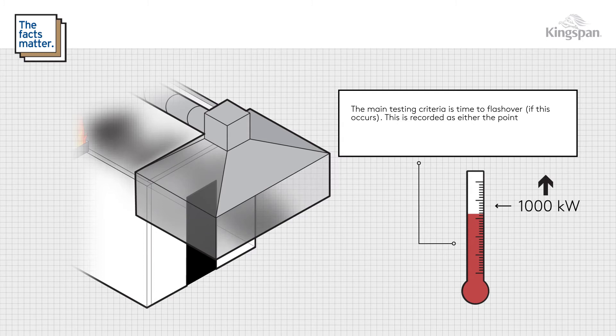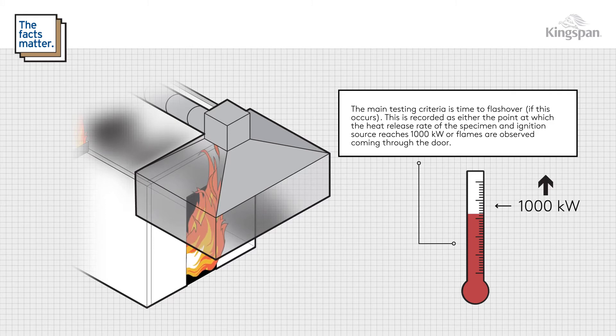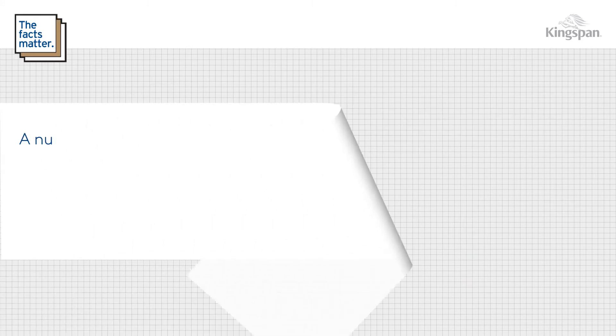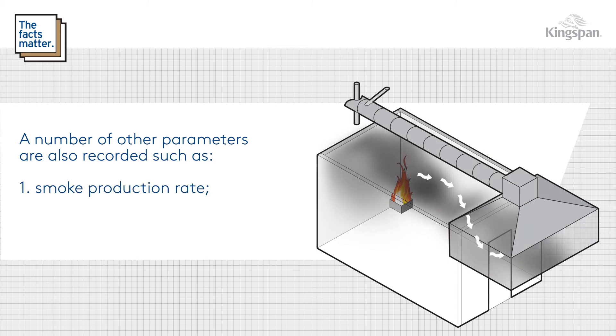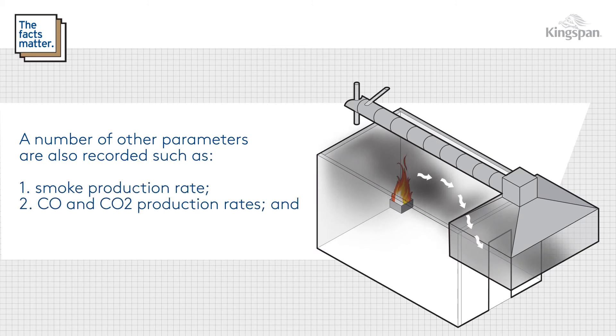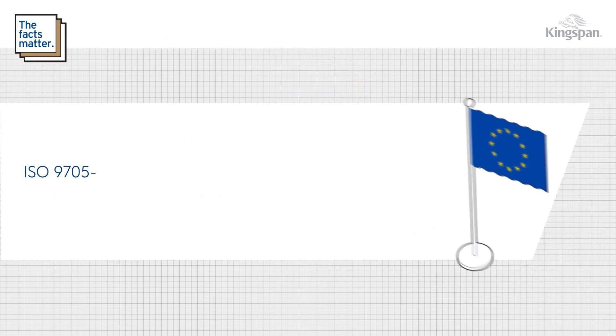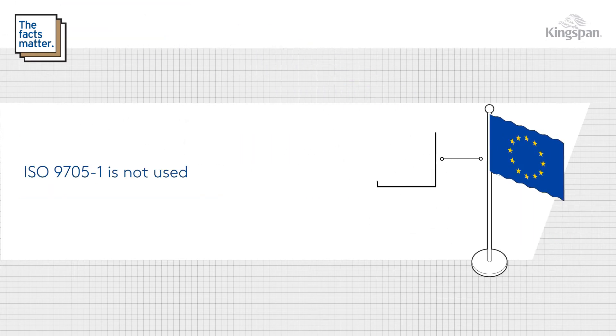The main testing criteria is time to flashover. If this occurs, it is recorded as either the point at which the heat release rate of the specimen and ignition source reaches 1,000 kilowatts, or flames are observed coming through the door. A number of other parameters are also recorded, such as smoke production rate, CO and CO2 production rates, and oxygen depletion rate.